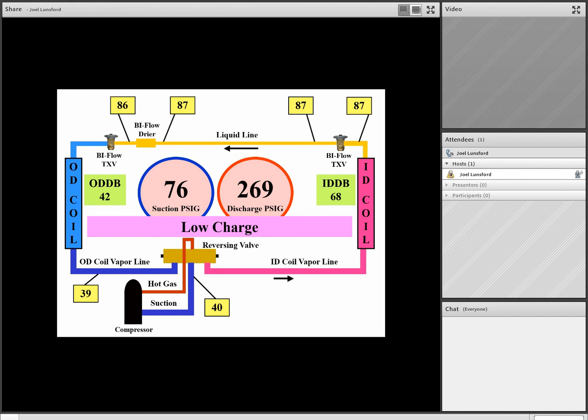Okay, team, in this example here, we have a 410A unit, and it's in the heating mode of operation. As we take a look at the refrigeration circuit and the pressures, we see that we have really low suction pressure for a 410A unit. And being in the heating mode of operation, we have considerably higher discharge pressure as well. So as we work this system through and we take a look at it, we notice that something that really jumps out at us is the indoor bi-flow TXV.